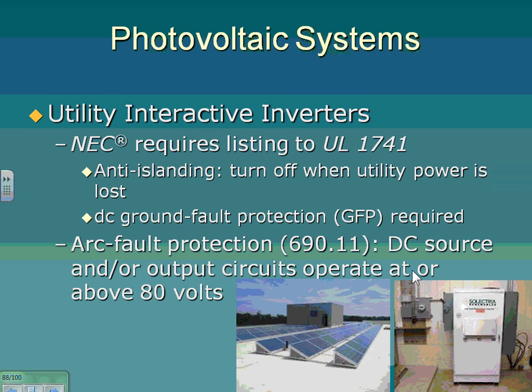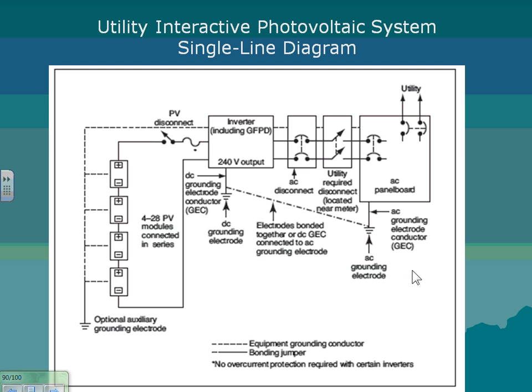Inverters, I'll show you interactive inverters, and a couple of disconnects that you have to have. This is really nice, it shows how the system is tied together. The only thing I want to show for the electrician is that you have two grounding electrode systems and you have to tie them together with a number 6 copper at least. You have a grounding electrode system for the inverter DC side, and one for the AC of your facility, and these two have to be tied together. The inverter is a non-separately derived system: the AC of the inverter is not grounded through the inverter, it's grounded through the utility. So that's very, very important.